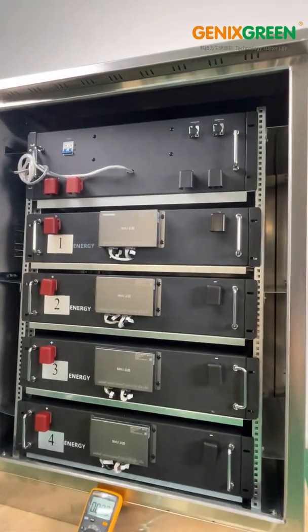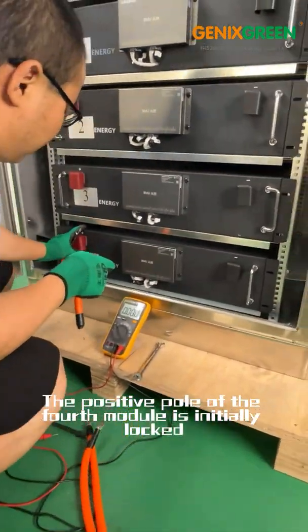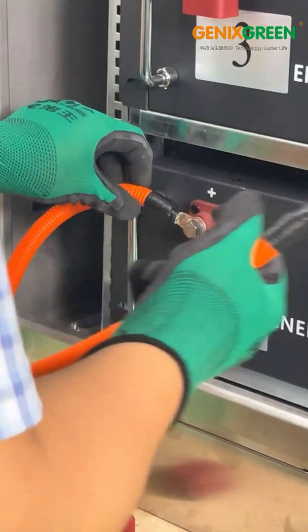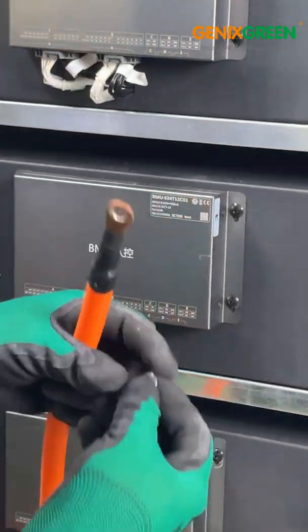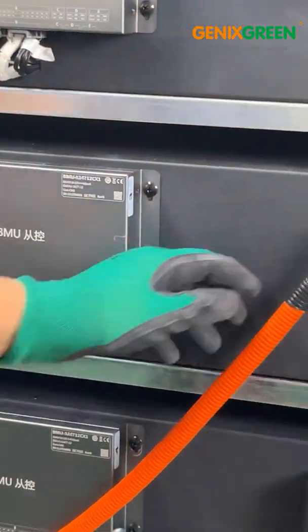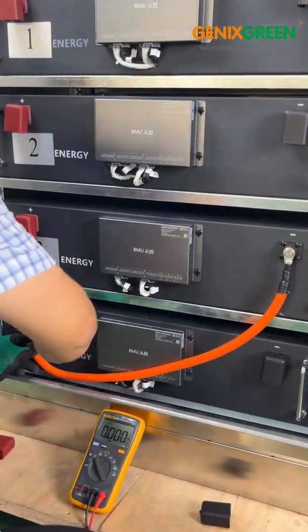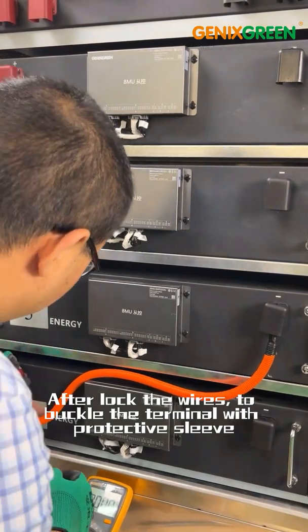Second step. Three high voltage power wires, same length. First, the positive pole of the fourth module is initially locked. Spring pads must be added. Because the current is large, the wire must be vertical. After locking the wires, buckle the terminal with the protective sleeve.